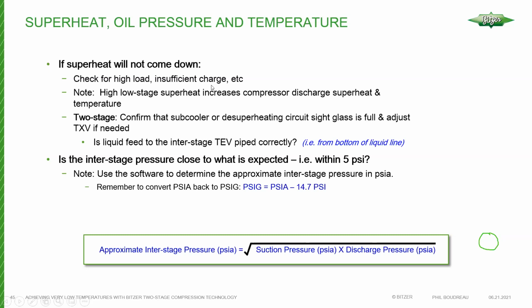Load is super high. But one thing I wanted to point out is when you are evaluating a two-stage compressor in the field, one neat thing you can do with a 6-cylinder compressor is, again, this is the same formula I had shown you before: you take the suction pressure and the discharge pressure, both in PSIA, multiply them together and take the square root of that number. And for 6-cylinder compressors, that should put you within about 5 PSI of what the software indicates.